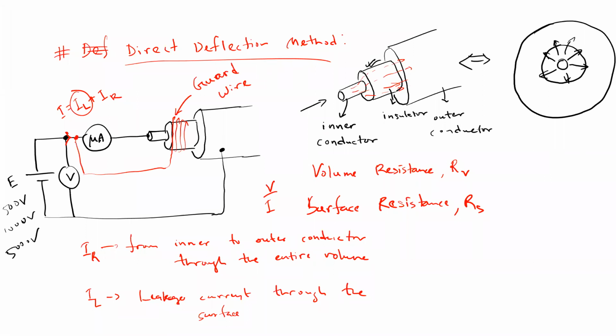Now the current IL, as this is a short circuit path, will bypass through this wire, and the current IR, which flows through the inner conductor, through the entire volume of the insulating material, to the outer conductor, will pass through the ammeter. In this way the two currents can be separated, and now the volume resistance RV can be calculated as V divided by IR.